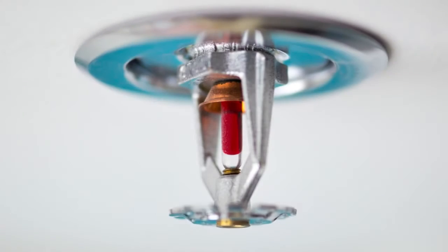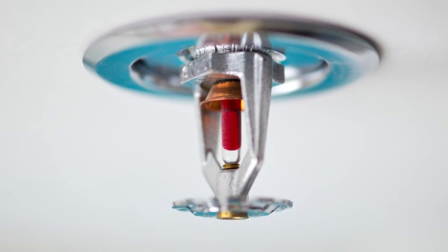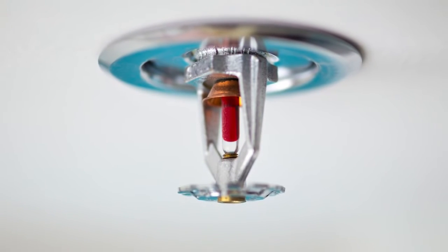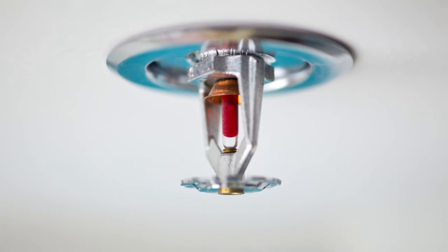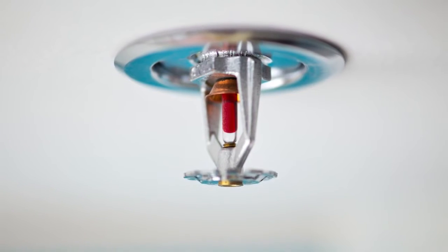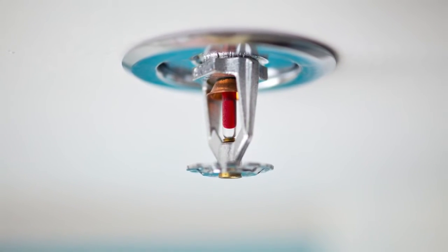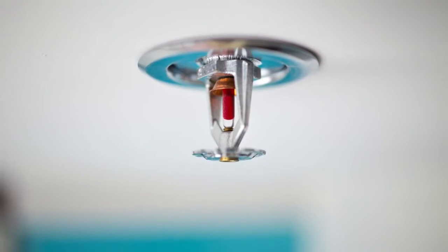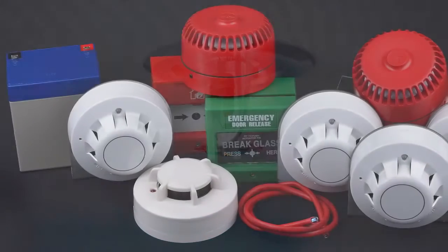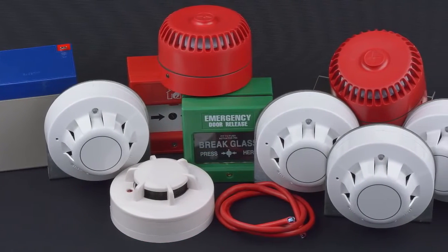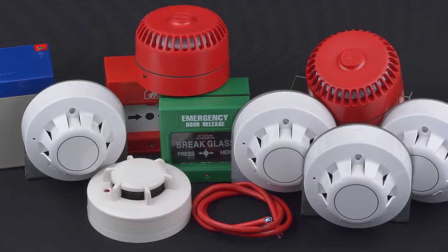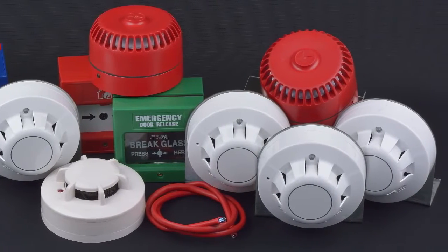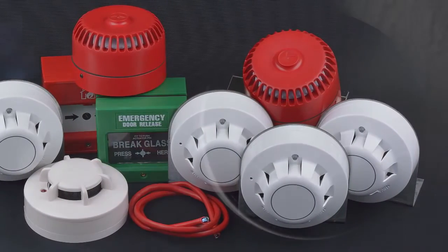The two most commonly used smoke alarms, mainly because they are inexpensive, are photoelectric and ionization detector alarms. The difference between the two lies in how they detect smoke particles. Depending on the conditions of the fire, one type is usually better than the other. Many other kinds of detectors exist that are more expensive and often situation-specific, such as needing to protect classified documents or computer servers. These tend to be much more sensitive and allow for many different levels of detection and alarm. The most common of these is aspiration detectors.